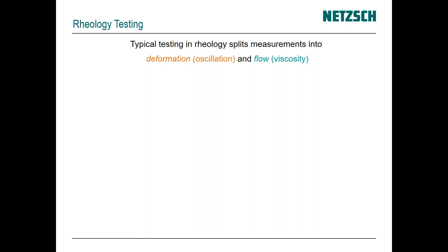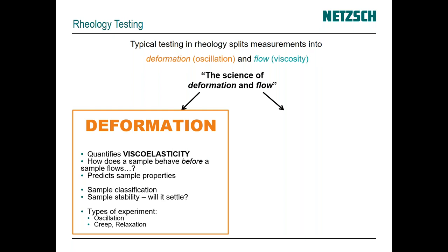In rheology we generally break testing up into two major categories. Deformation or oscillation is the first mode — cyclic testing, low amplitude non-destructive testing. The other category would be flow or viscometry, where we're shearing a material. When we do our oscillation tests we start quantifying the viscoelasticity in a material.